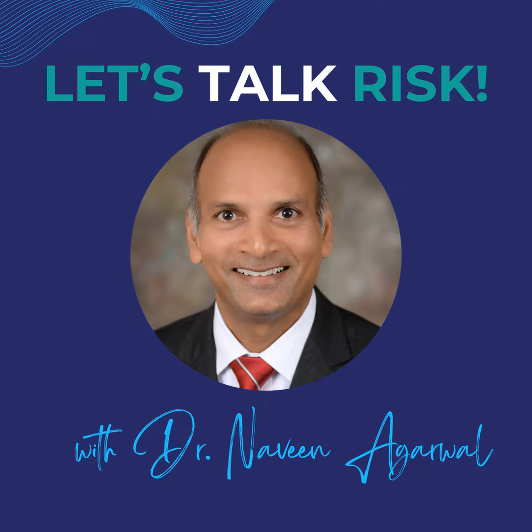Yeah, it's absolutely a concern. It's one of the major hazards that are identified just in the decades of automation research. But it's also brought up by the FDA in that PCCP guidance that I mentioned. So they actually explicitly talk about that and refer to that you may need to be monitoring for that in, say, your clinical studies where you're having people do repeated uses and starting to monitor or probe down for that.